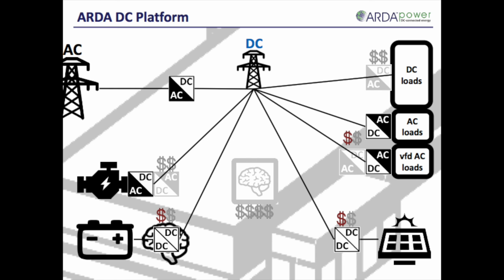A simple DC-AC grid inverter is used to interconnect with the macrogrid, which is used only for the export and import of energy, and which completely eliminates the need for expensive and bulky static switches required for AC systems. When the macrogrid goes down, the system continues to operate with no change in state and reacts in the same way that it would if a connected genset were to fail, or when solar production ceases at night, and with no latency at all.